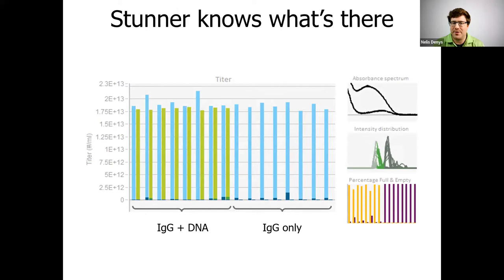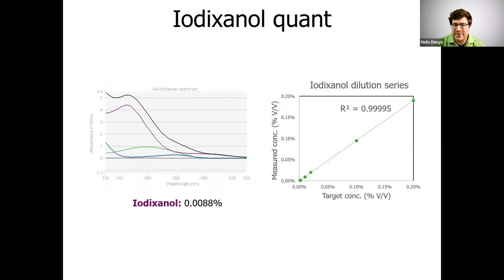If you try to fake out Stunner, this is what happens. If you put IgG and DNA together in a sample to mimic a full capsid, or just IgG alone to mimic an empty capsid, Stunner knew what was there. You can see that almost everything is in light green and light blue, because there's no capsid peak in the DLS — you can't fool Stunner. If iodixanol is part of your process, it's also useful to know exactly how much iodixanol you have in your sample and to check iodixanol concentration after each buffer exchange. Stunner can detect iodixanol in your sample as low as 0.0005% by volume.